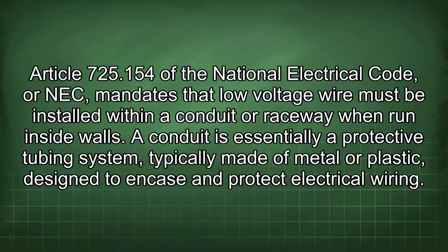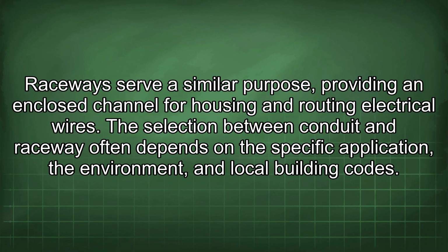725.154 of the National Electrical Code, or NEC, mandates that low-voltage wire must be installed within a conduit or raceway when run inside walls. A conduit is essentially a protective tubing system typically made of metal or plastic, designed to encase and protect electrical wiring. Raceways serve a similar purpose, providing an enclosed channel for housing and routing electrical wires. The selection between conduit and raceway often depends on the specific application, the environment, and local building codes.